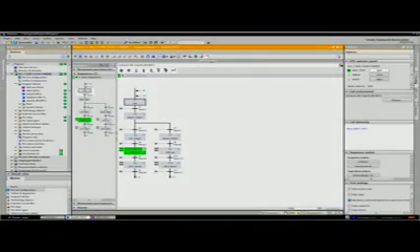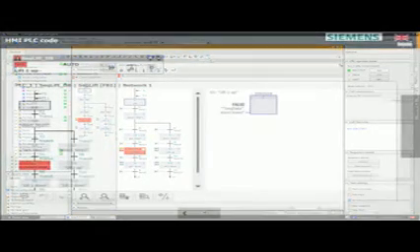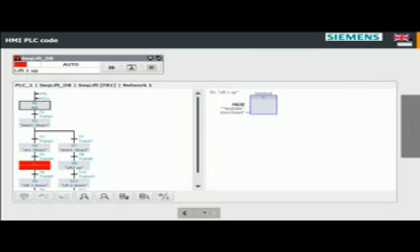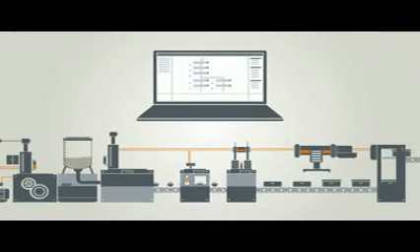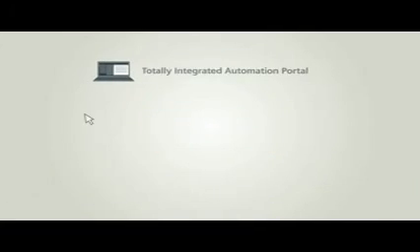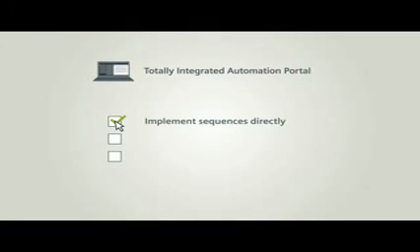By initiating the monitoring function, you can now monitor the sequencer online, both in the navigation tree and in the operating range. If there are faults in the routine, the step affected is marked in red. This greatly facilitates troubleshooting. The monitoring of an active sequence can be displayed on an HMI device. This enables troubleshooting even without a programming device. With a programming in Graph, you can implement the routine in your plant directly one-to-one in sequences.